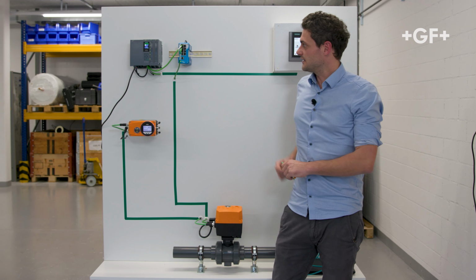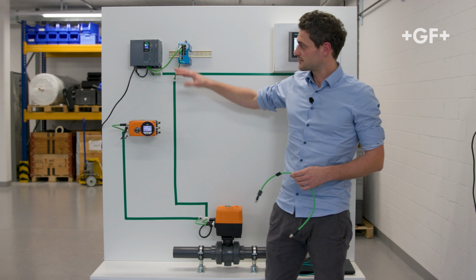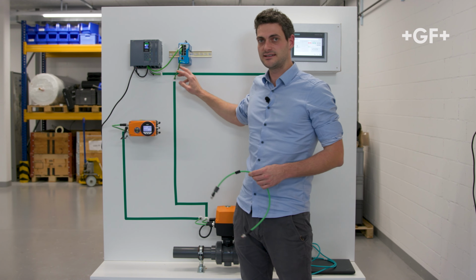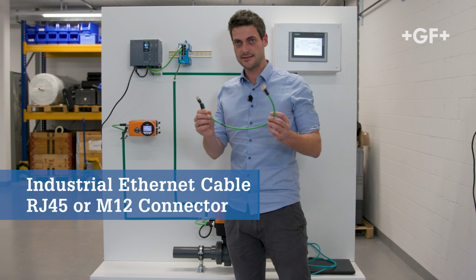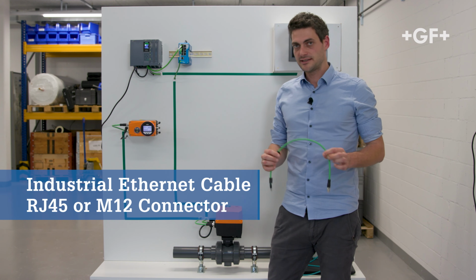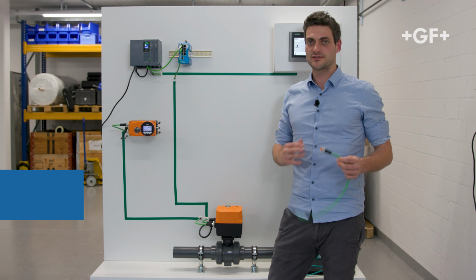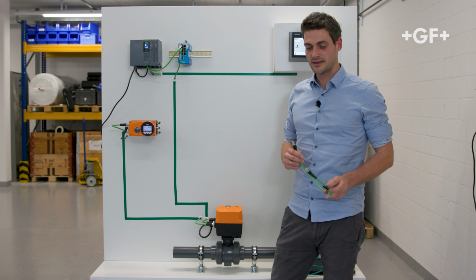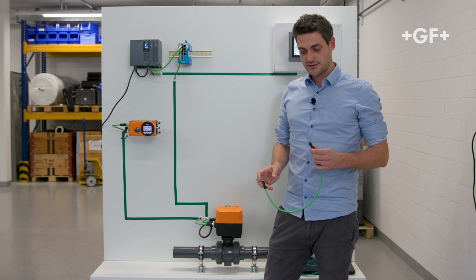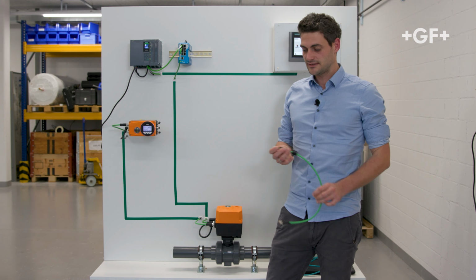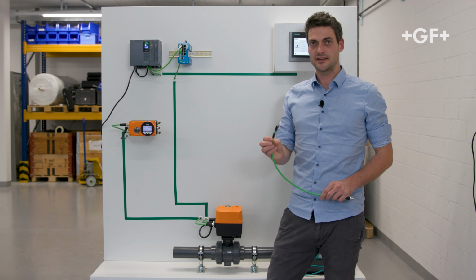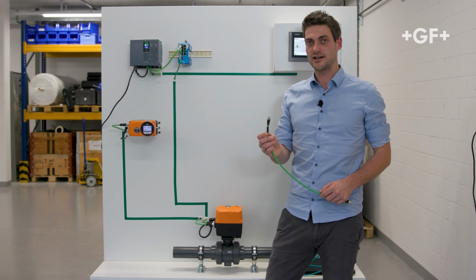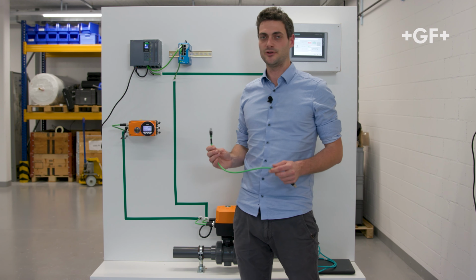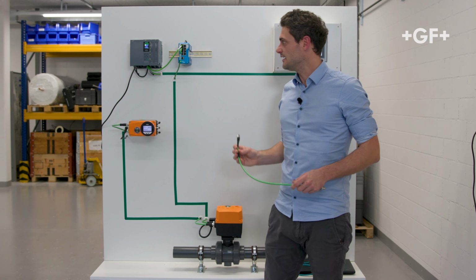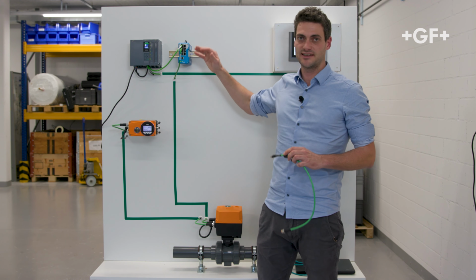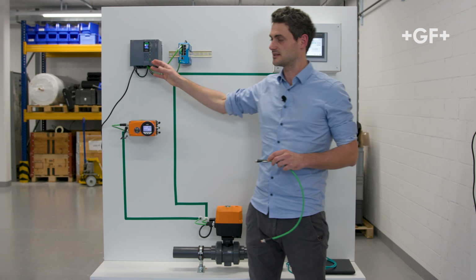Let's take a look at the interconnection itself. So all the green cables, which you can see here, are the so-called Ethernet cables, like this. This cable needs to be of category 5, but you also can use higher cable categories. In terms of connectors, there are two different possibilities. On the one hand, we have the typical known Ethernet connector, RJ45, which you might know from your office or home installation. This is typically used outside of the field level, so for switches and the PLC itself.